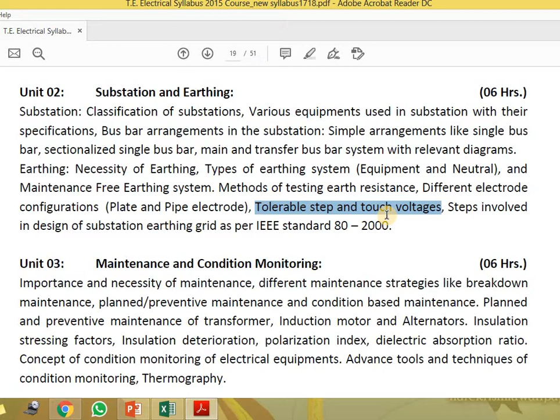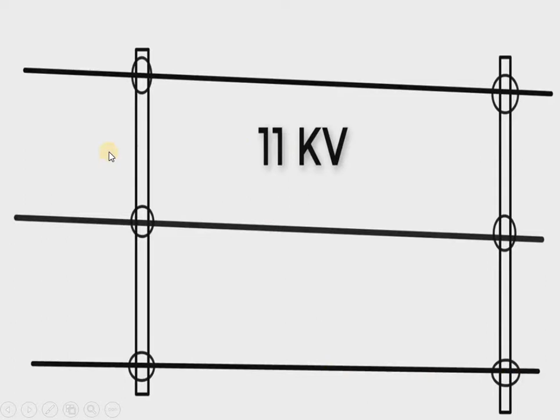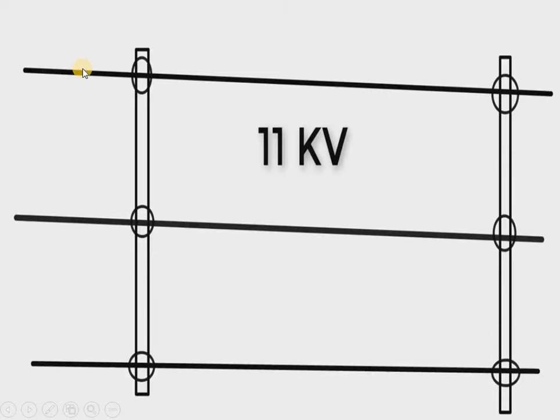Let's say we have a 3-phase live conductor carrying 11 kilovolts, with a sending end and a receiving end. Let's say the Y conductor breaks due to an environmental condition or human mistake. If the conductor breaks, this Y conductor falls on the ground at this point.